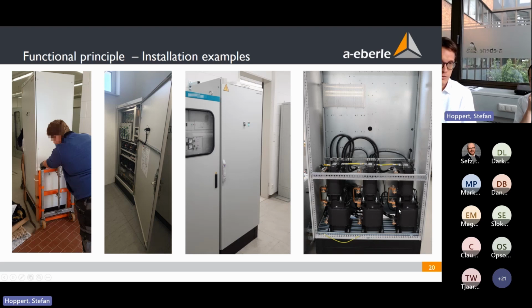Here we see some pictures of how the installation is made. On site, we have seen a good example of how to move the cabinet. This is a small wagon where you have to remove the wooden pallet before, and then you can put the cabinet on the wagon. Then you do not add a lot of height, so you can go through almost all the doors. If the cabinet is 2 meters high, then this will make maybe 2 centimeters more, so you can easily go through a normal door.